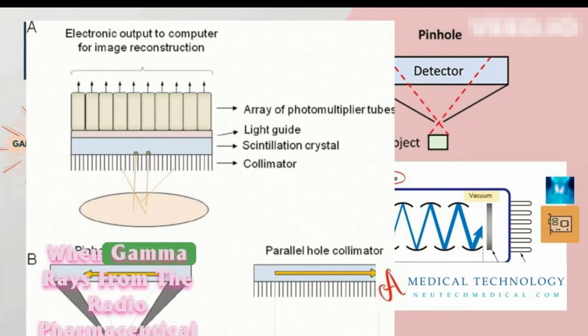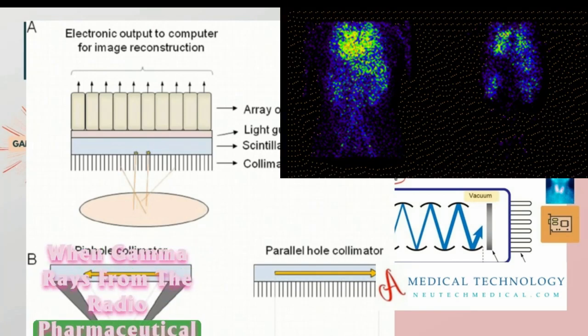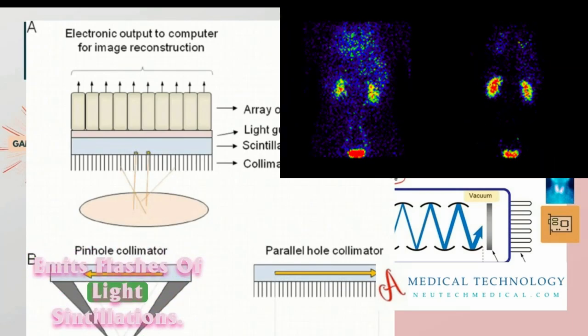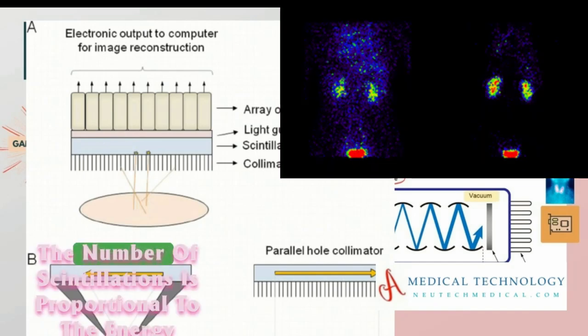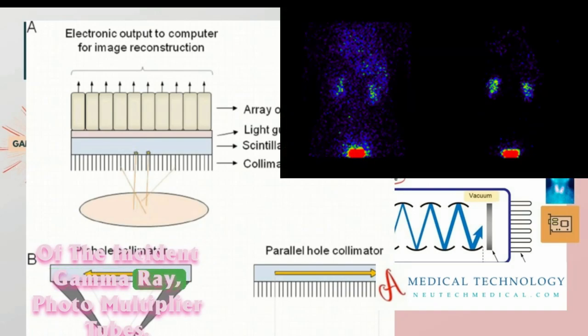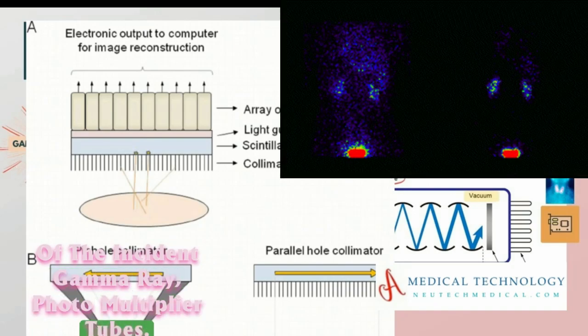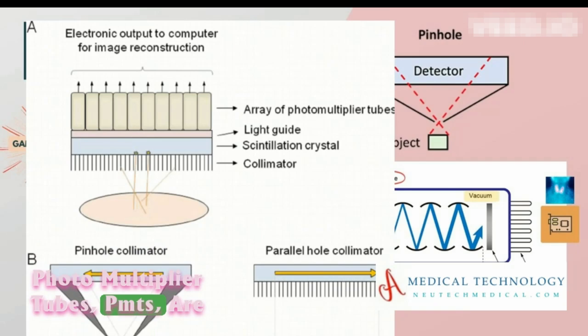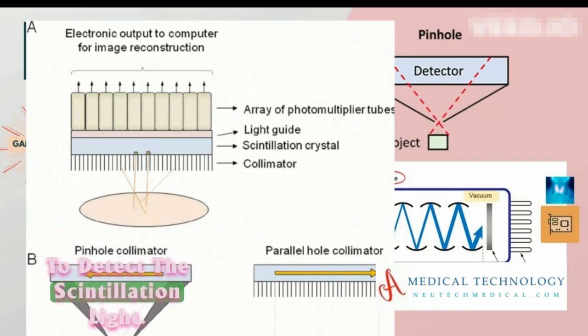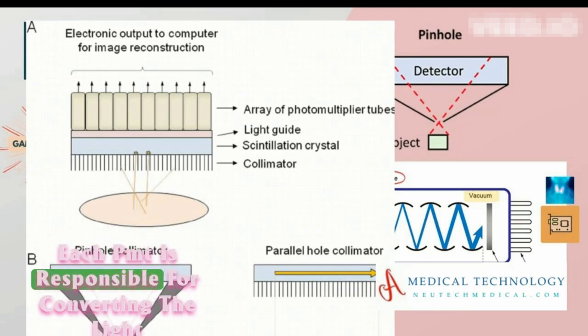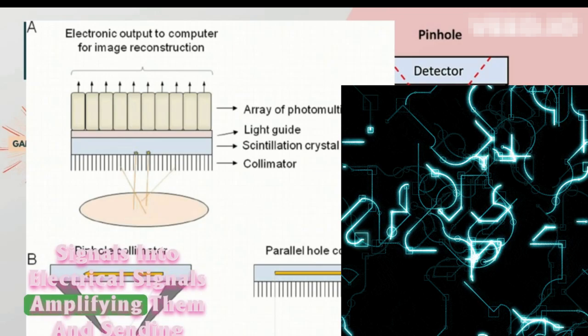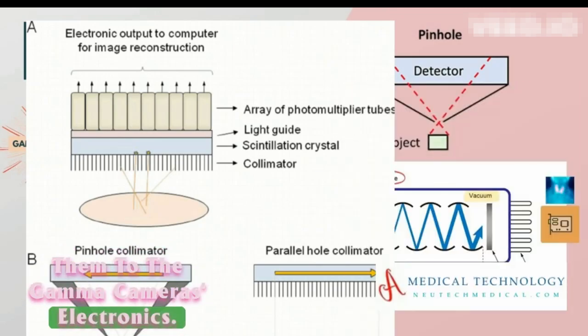Gamma ray detection: When gamma rays from the radiopharmaceutical interact with the scintillation crystal, the crystal emits flashes of light (scintillations). The number of scintillations is proportional to the energy of the incident gamma ray. Photomultiplier tubes (PMTs) are positioned around the scintillation crystal to detect the scintillation light. Each PMT is responsible for converting the light signals into electrical signals, amplifying them, and sending them to the gamma camera's electronics.